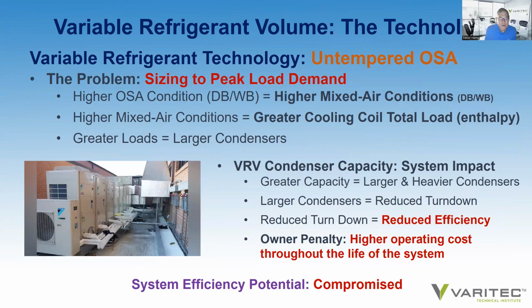So the problem is that if you design a variable refrigerant system with untempered outside air and you size to peak load demand, higher outside air condition results in higher mixed air conditions at the air fan coil unit cooling coil. Higher mixed air conditions equal greater cooling coil total load. Greater loads mean larger condensers. So you have to upsize the condensers if you designed the peak summer load that you would need to do to condition the untempered outside air.